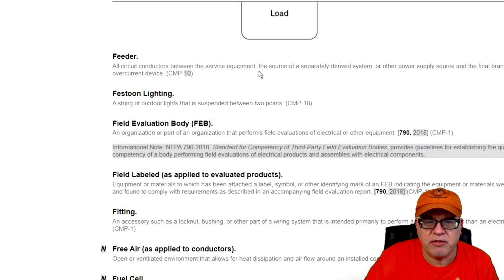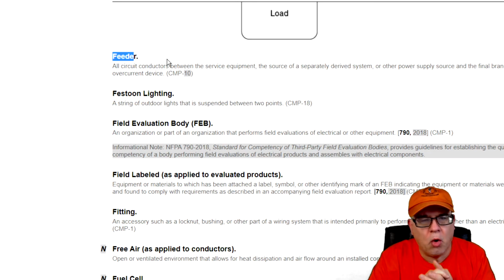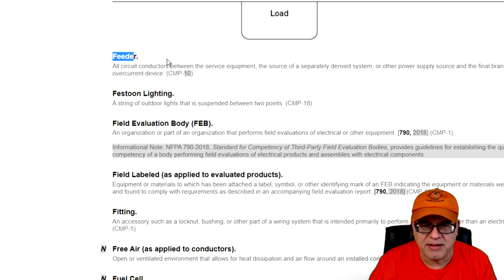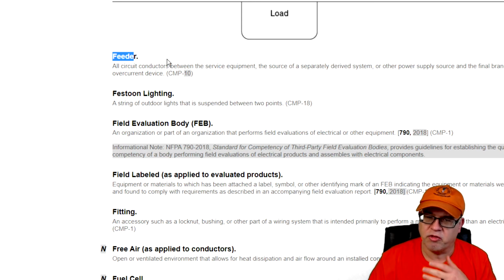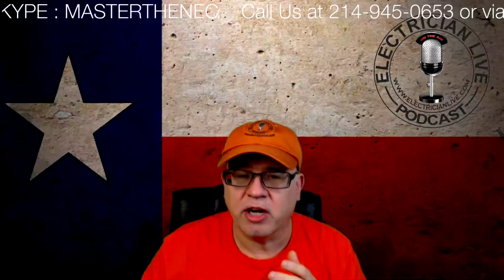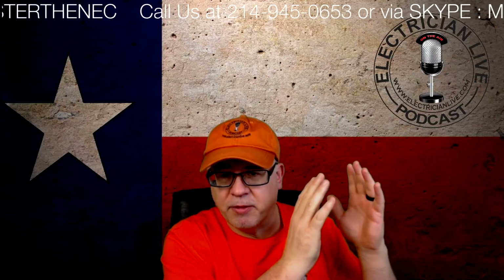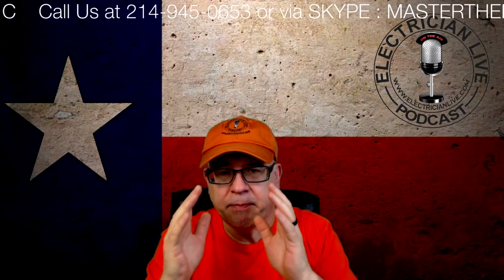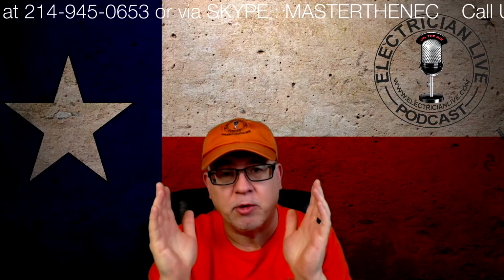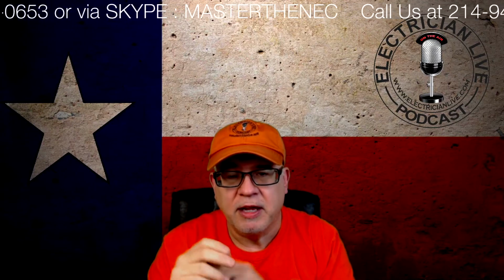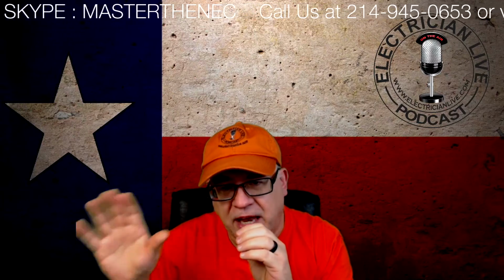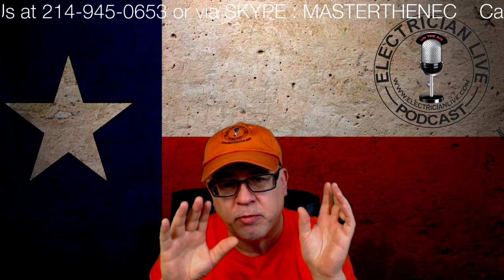Okay. Other things to remember is the term feeder, obviously used a whole lot through the NEC. Biggest difference for people to realize is that a feeder is all circuit conductors between service equipment and the source of a separately derived system or other power supply sources to the final branch circuit overcurrent device. So, easiest way to explain this to people and have a good understanding of feeder is that I have my service here, and from my service I'm feeding a panel downstream. I'm feeding that panel. In that panel downstream, remote distribution panel, some people call a sub-panel, whatever floats your boat. In that, I'm going to have individual circuit breakers or fuses that are going to go out from there out to whatever my load would be, receptacles, lights, a motor, or whatever it would be. And that is the final branch circuit overcurrent protected device. So that's a branch circuit out to the loads. From the service panel to the actual remote distribution panel, that's a feeder.